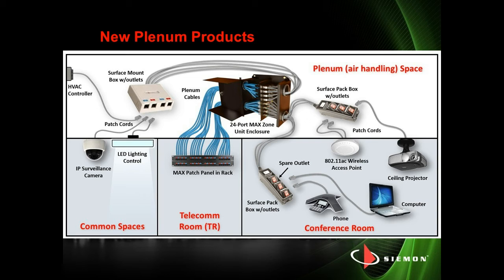Increased reliability: with a PoE system you have the ability to maintain continuity in the event of a power failure. It's much easier to maintain uninterruptible power over structured cabling than for a standard lighting system, where you may have to switch on a generator for certain sections of the building, or deal with breakers. It becomes quite an ordeal.